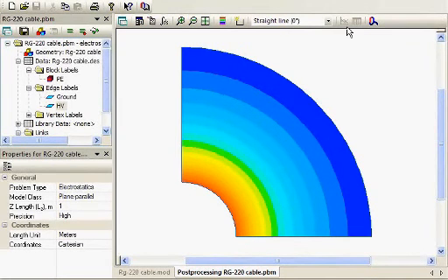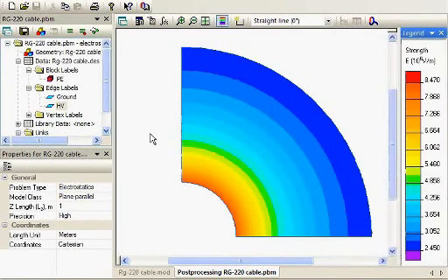So just a couple other things I would point out. Again, that field stress is within the dielectric capabilities of the cable. The thing you start to worry about is you can see even at the outer edge of the cable, it's creeping up towards about 3 megavolts per meter. And that's getting up very close to the corona onset voltage or breakdown threshold for air insulation. So given the fact that you can have small air gaps between the dielectric material and the braid material, you could start to see corona develop at this OD of the insulation.